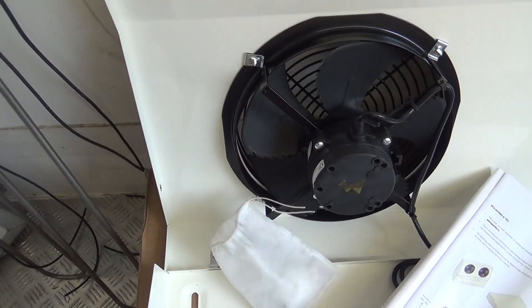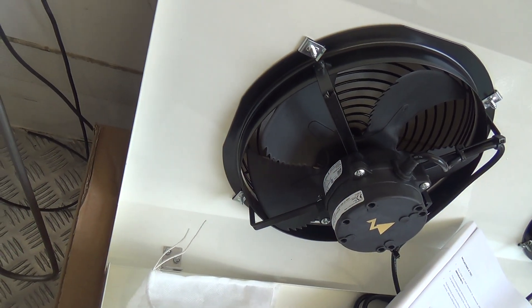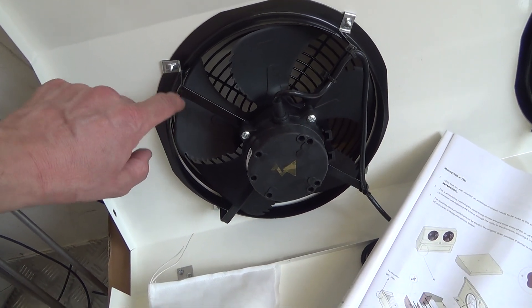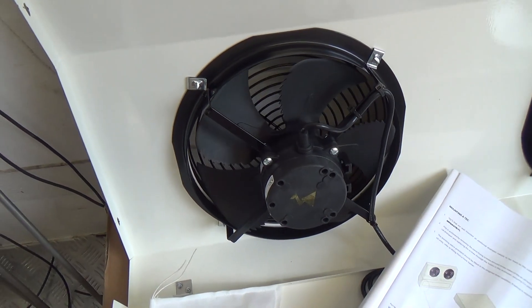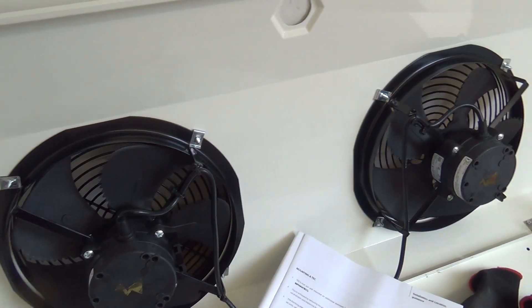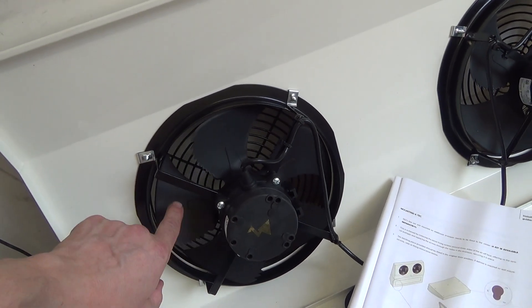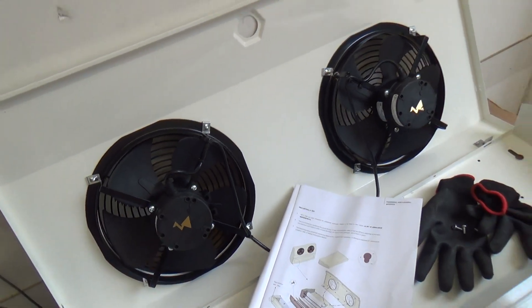I've noticed they've changed the motors on these. They used to be Elko — I could be wrong — but they used to be plastic and I had a couple where the legs sheared off in transit. You'd fit them then have to go to the wholesalers and go back to fit replacements, ending up doing two trips. Anyway, they've gone back to being metal which is much better, and they're little EC fan motors — reliability-wise I've had no problems with these on these little units.